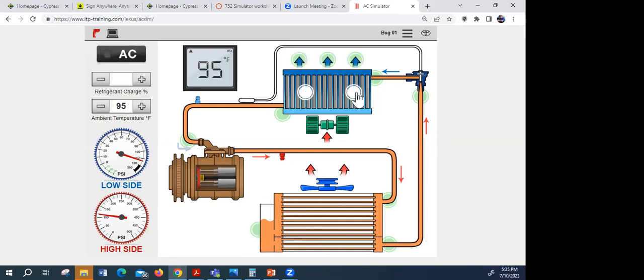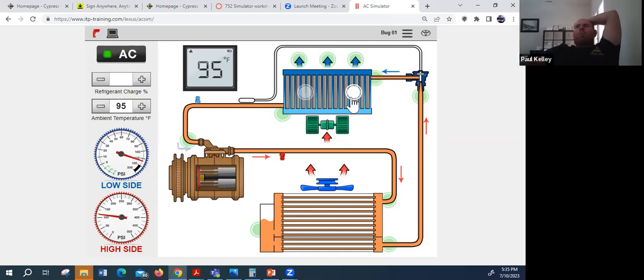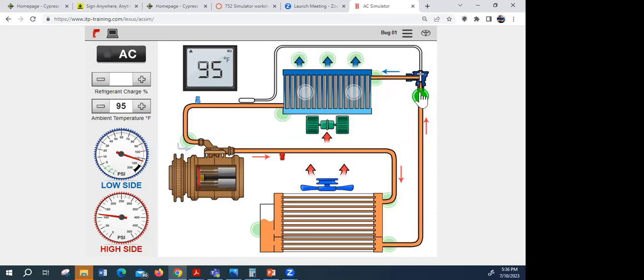On the evaporator temperature sensor, it doesn't necessarily show exactly where that's at. I'd say it's probably closest to here, because this is actually the bulb for the TXV, similar to a sensor. The actual sensor would be poked in here somewhere. Looks like I see 95 everywhere. Yep, all the lines are the same color. That's bad, yeah, so everything's 95. All right, cool.